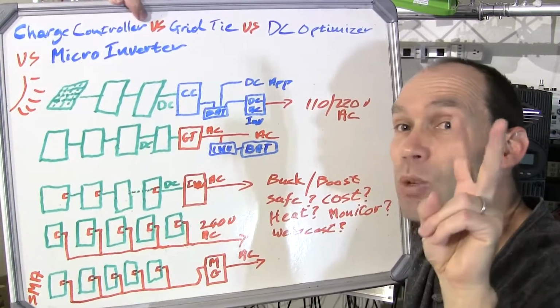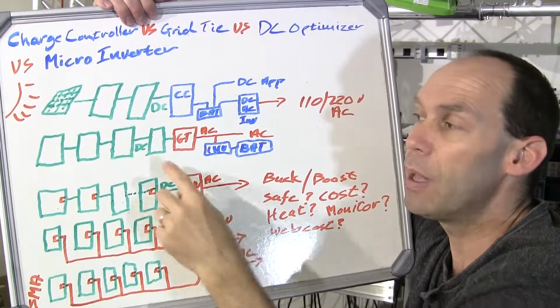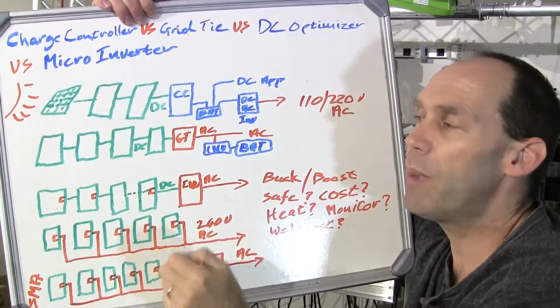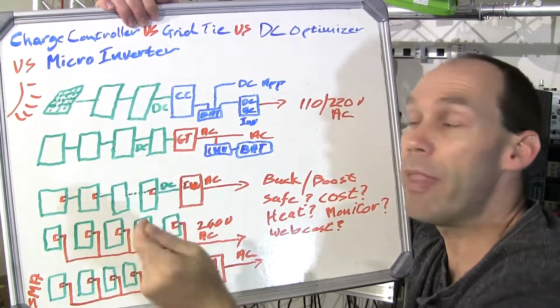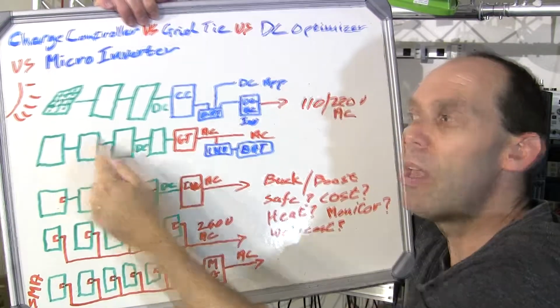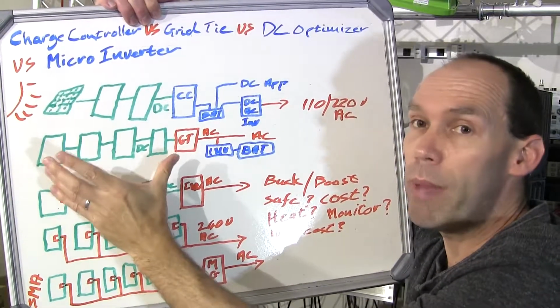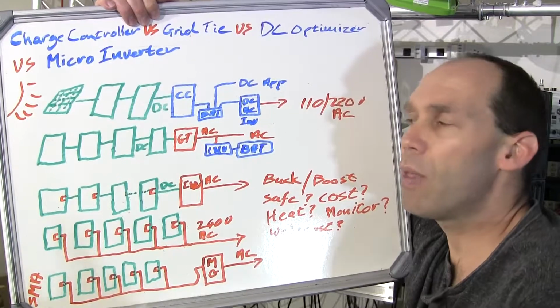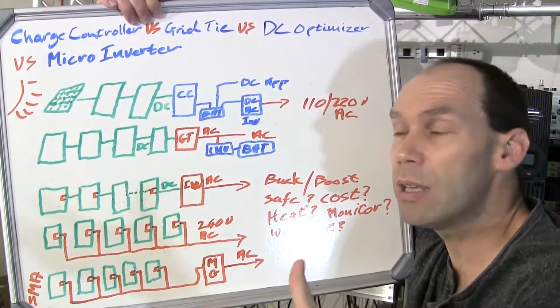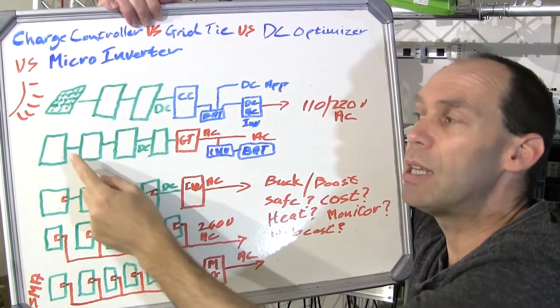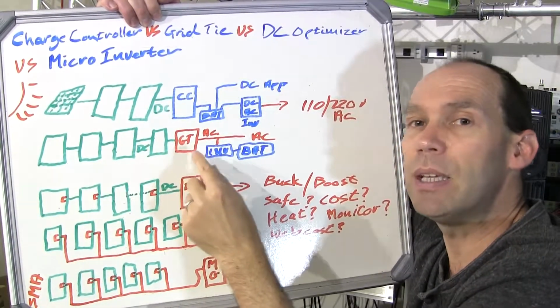It sees it as one virtual solar panel. It doesn't see the individual solar panels. So it's trying to do MPPT across all these panels. And that's why it's important that you use the same type of panel and that they're all matched. Now, for one, you're not going to know from the manufacturer whether they're performing exactly the same, but they should be close enough.